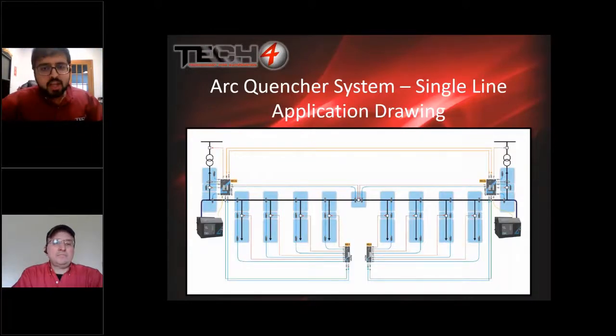So here's just an application drawing, an example of how the Tech4 arc quencher system looks. So that's the AQ1000 device, which receives a trip signal from the AQ110 arc flash protection relay. So when it senses light, which is a flash, and one of the point light sensors picks it up, and it simultaneously detects a high current, it sends a trip signal to the arc quencher device, and all of the process again takes place in less than 4 milliseconds.